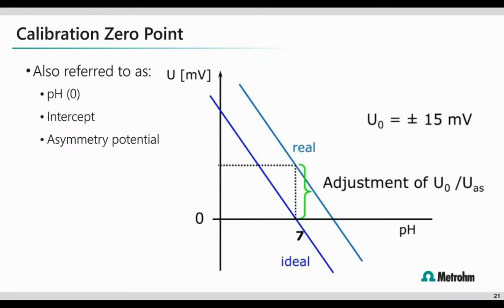One of the results of the calibration is the electrode 0 point. Sometimes you may hear this referred to as pH 0, intercept, or the asymmetry potential. Essentially what we're looking at here is, we've got that theoretical 0 millivolt reading at a pH of 7. In the real world, we would make an adjustment from that theoretical value, and that is the asymmetry potential.